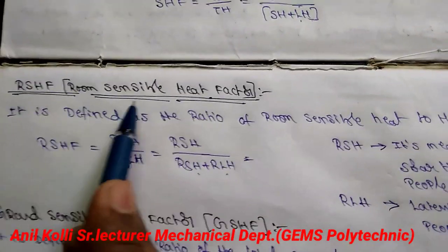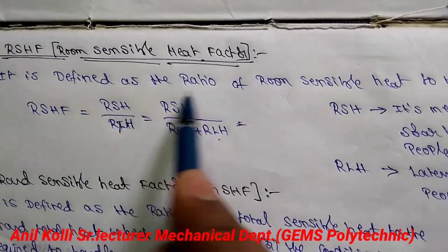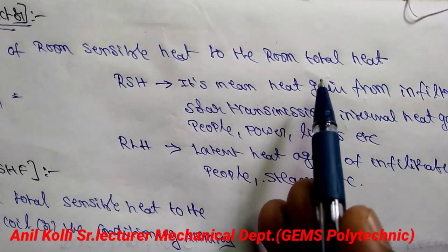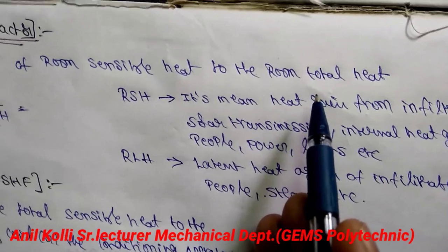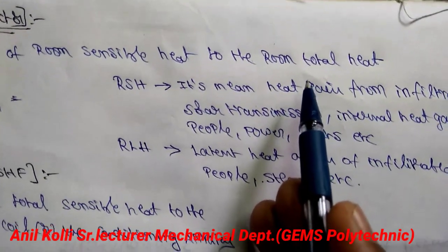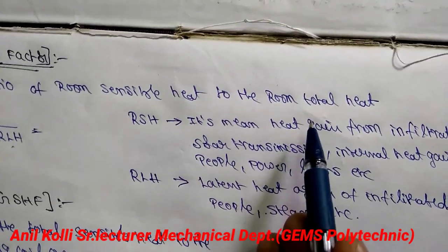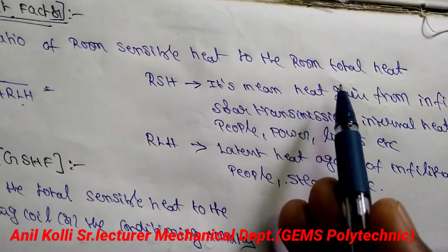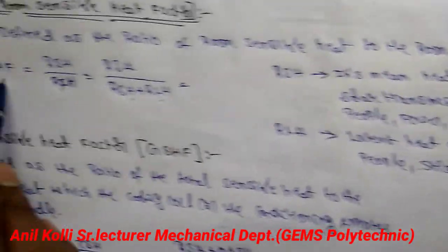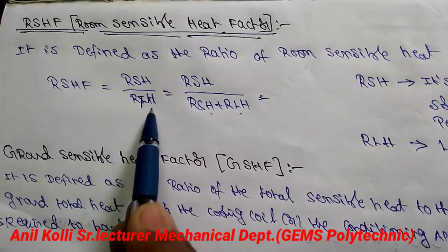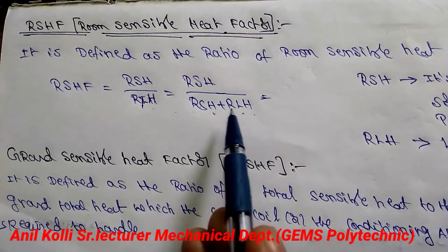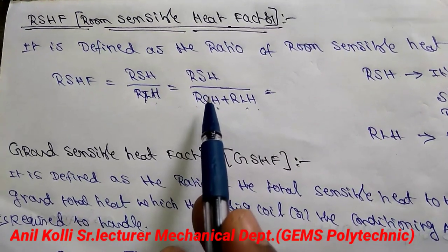What is room sensible heat factor? It is defined as the ratio of room sensible heat to the room total heat. When we talk about a room — for example, a hall or an auditorium — we can call it the auditorium sensible heat factor. Room sensible heat factor equals room sensible heat divided by room total heat. Room total heat means room sensible heat plus room latent heat.